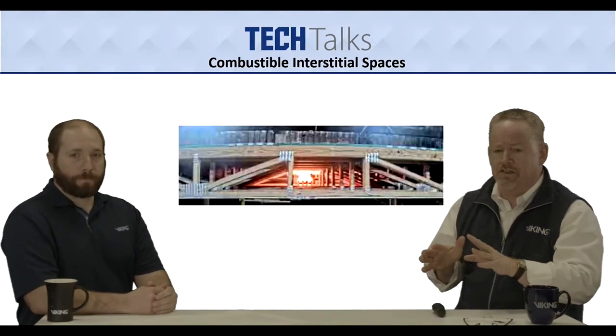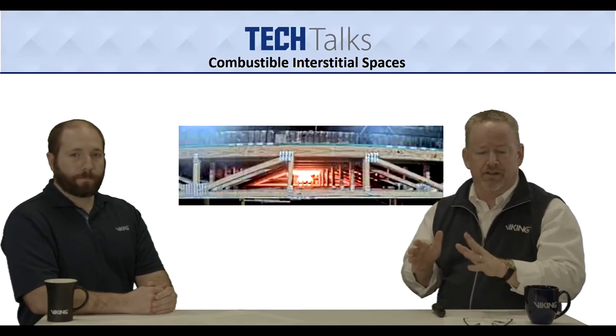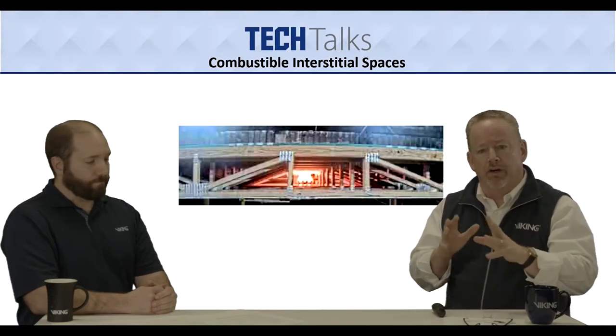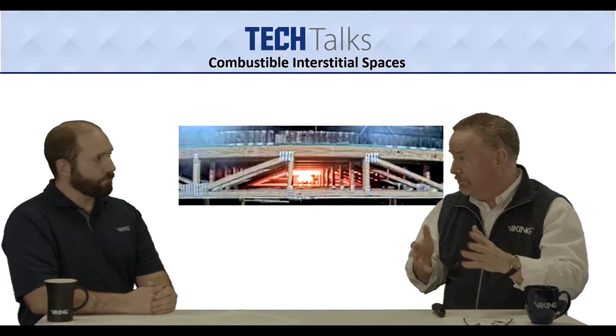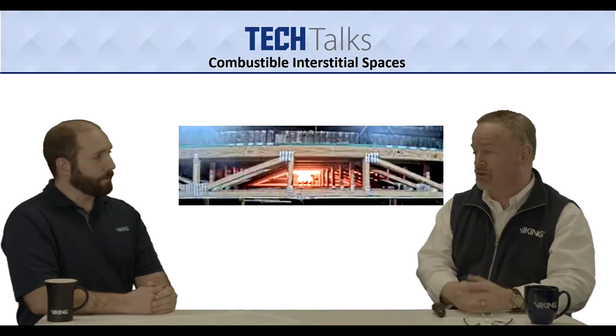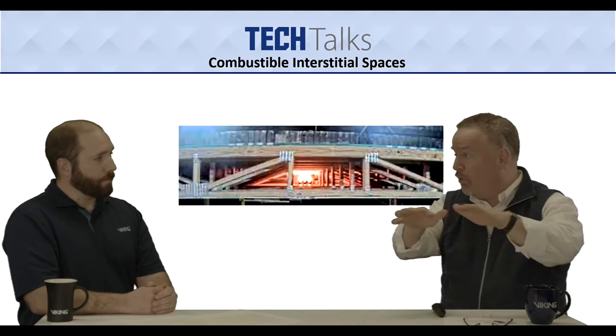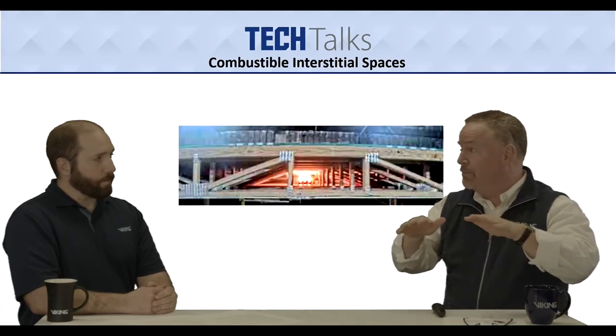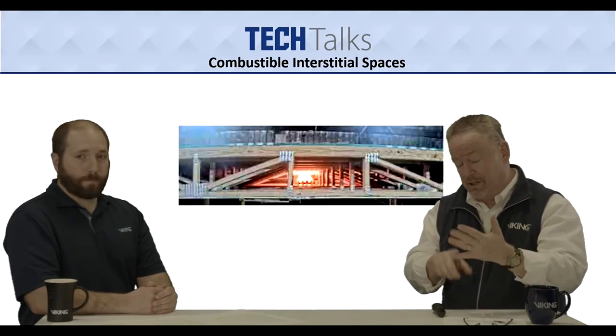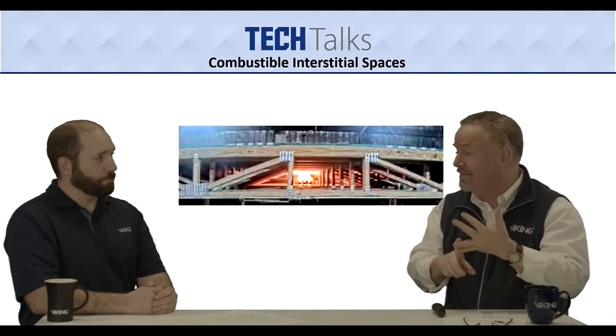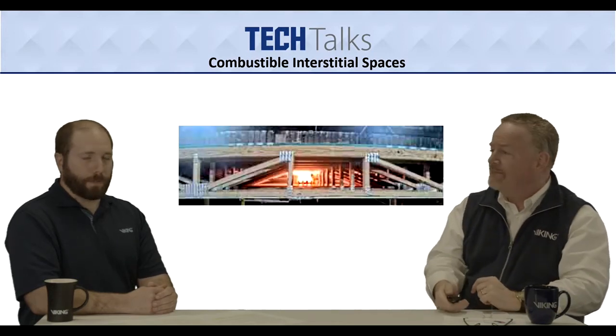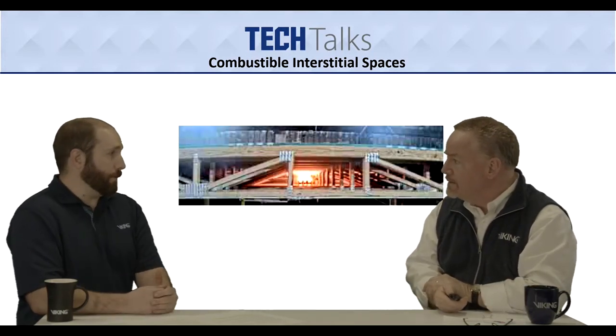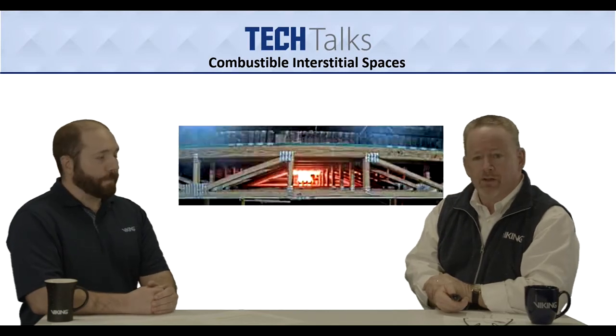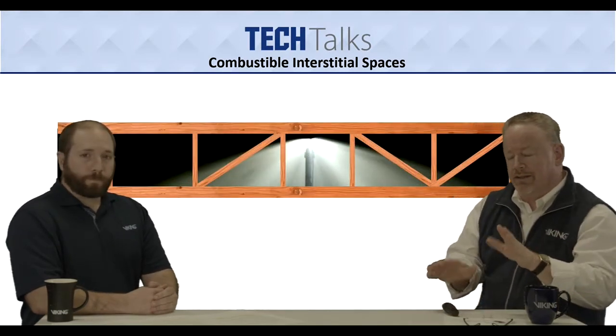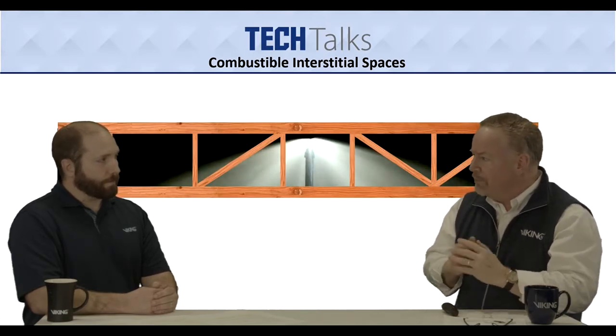First of all, this is a look at the test fire that is run at UL for evaluating our combustible interstitial space sprinklers. The idea here is to deliver water into these spaces with a spray pattern that can take into account the obstructions provided there and the narrow space, right? Absolutely. So the idea is to develop this full-scale fire test and see how it performs. This particular little video does demonstrate what these spray patterns look like.